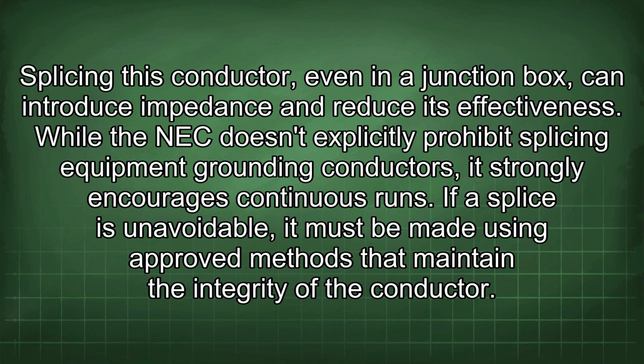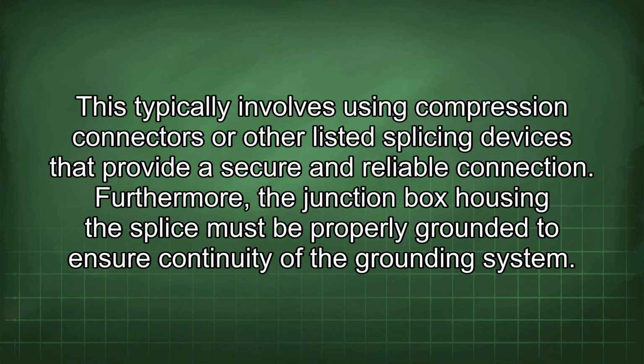While the NEC doesn't explicitly prohibit splicing equipment grounding conductors, it strongly encourages continuous runs. If a splice is unavoidable, it must be made using approved methods that maintain the integrity of the conductor. This typically involves using compression connectors or other listed splicing devices that provide a secure and reliable connection. Furthermore, the junction box housing the splice must be properly grounded to ensure continuity of the grounding system.